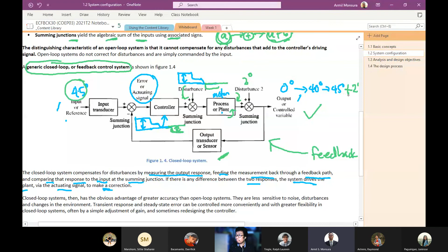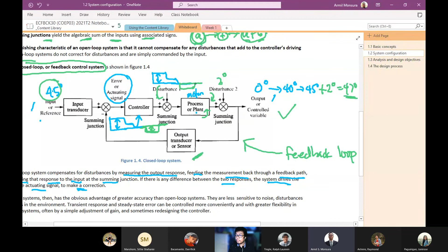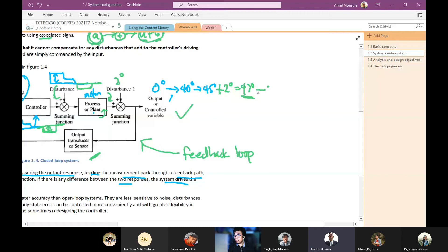So it would actually move in an opposite direction as what happened here. Kung siya ay clockwise, for example, dun sa case na kulay blue, in the case of when there's a difference of 2 degrees, counterclockwise naman yung gagawin niya. So therefore, pabawas ito, from 47, bababa yan towards 45. So mangyayari yung cycle na yan until such time that this error signal becomes 0, and therefore the controlling signal also becomes 0.